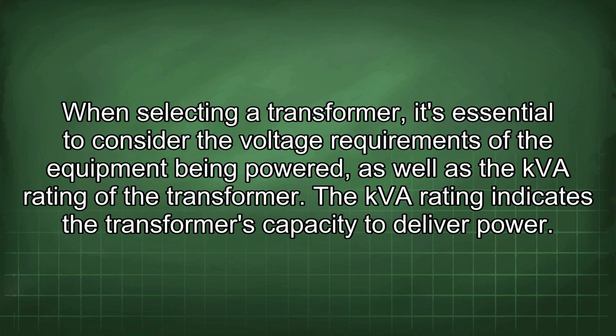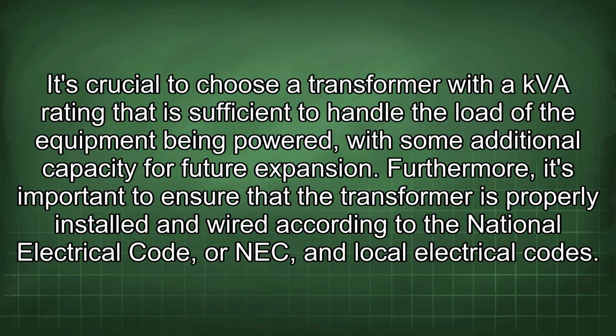When selecting a transformer, it's essential to consider the voltage requirements of the equipment being powered, as well as the kVA rating of the transformer. The kVA rating indicates the transformer's capacity to deliver power. It's crucial to choose a transformer with a kVA rating that is sufficient to handle the load of the equipment being powered, with some additional capacity for future expansion.